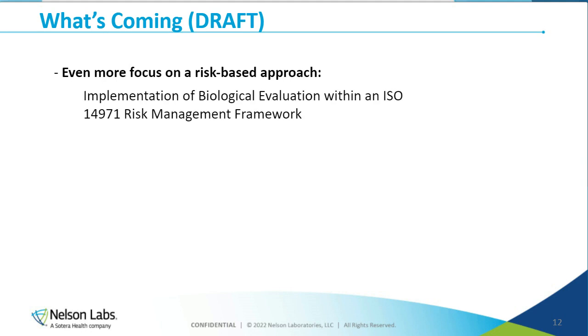So when we talk about the new draft, there is even more focus on this risk-based approach. They're trying to pull in ISO 14971, which talks about the risk management framework in general, into ISO 10993-1. So that's really good. That brings in that you really need to know where to pull the right information, what information you can use, and really sets the stage for a risk-based assessment.